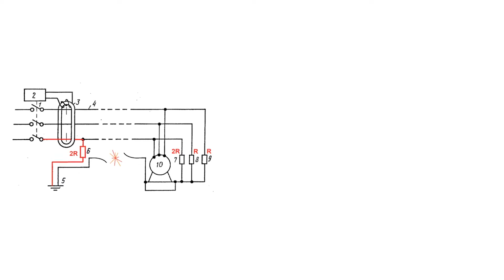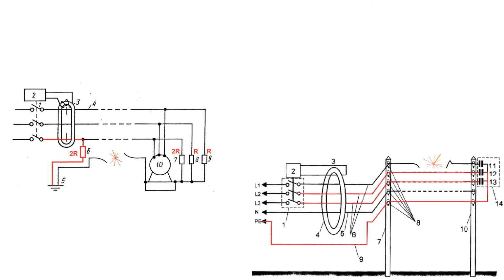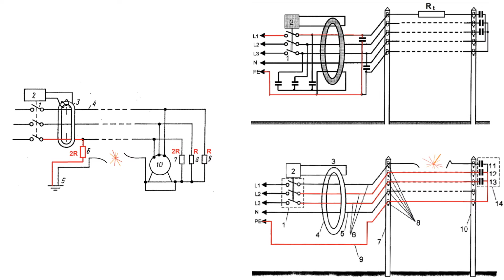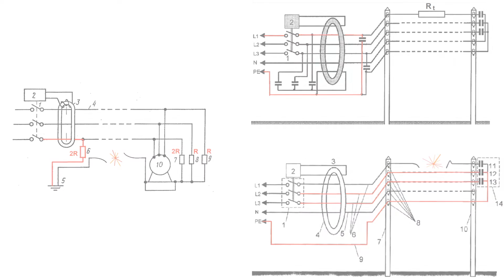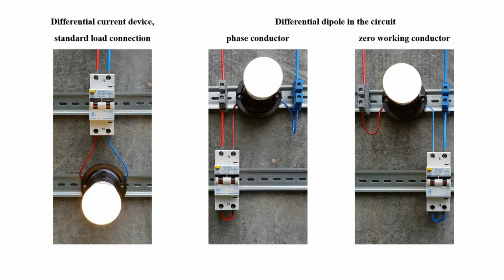Before continuing, let me remind you of two steps that we have already climbed. First, in the previous series, the principle of responding to damage to conductors and connections was noted. The short wording reads: shutdown in case of breakage, deterioration of conductivity and arc is provided if balance of the differential sensor currents is achieved only if there is no damage to the connection circuit. Second, the basic element for creating an automatic controller is presented.